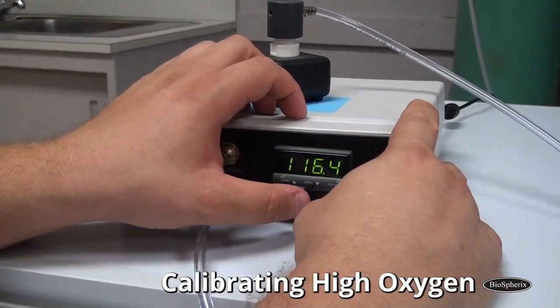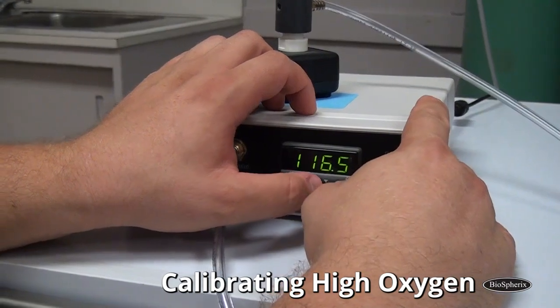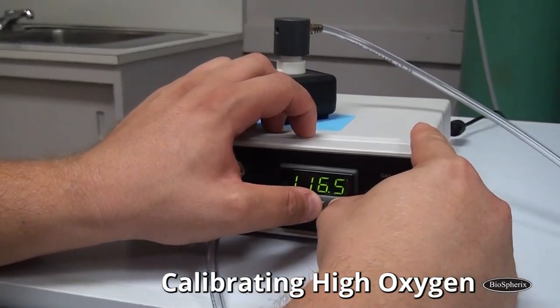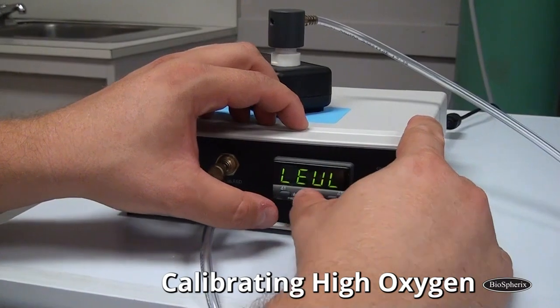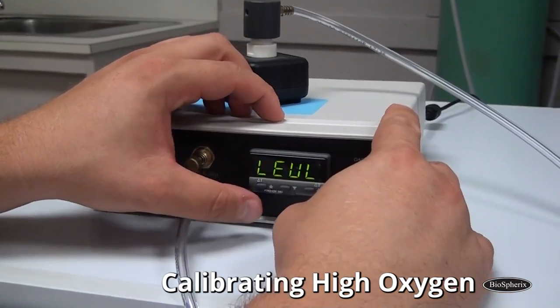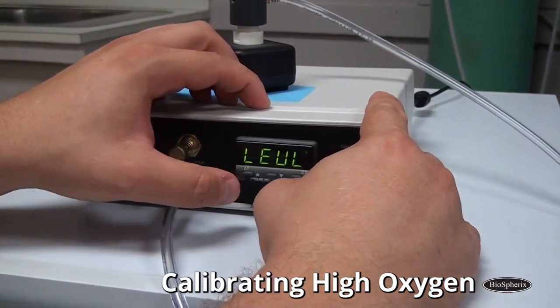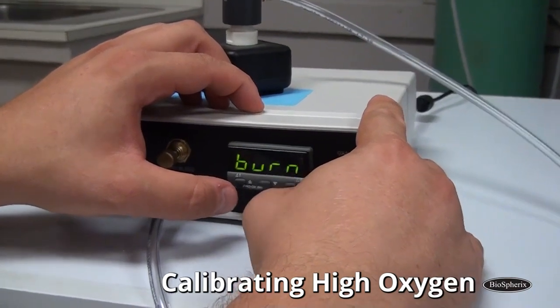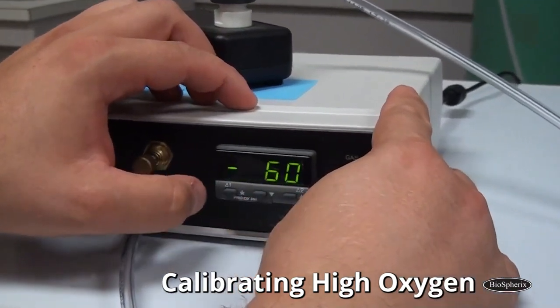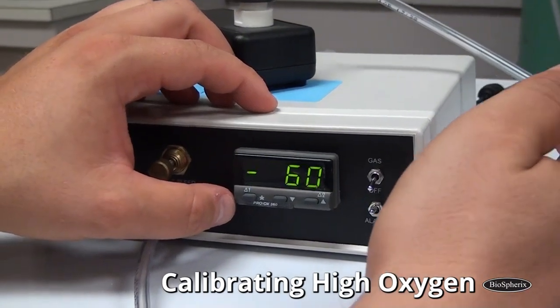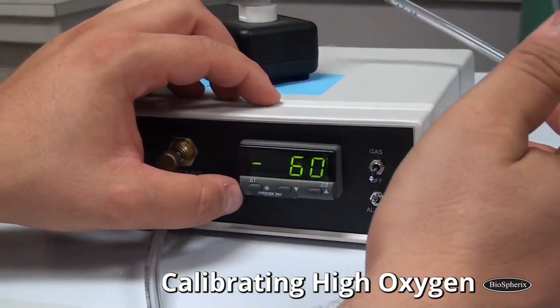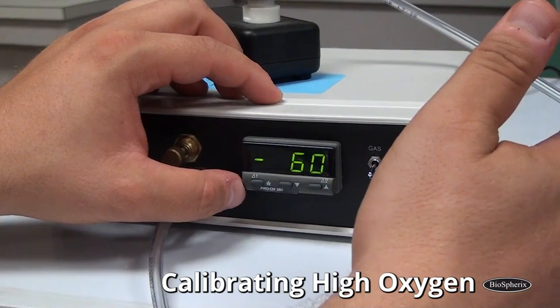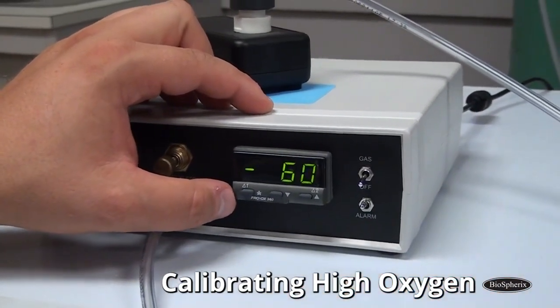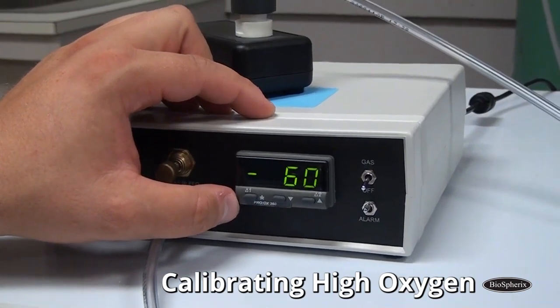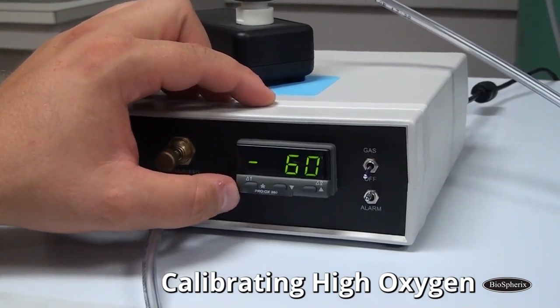It's a coarse adjustment. It's in the program mode, so we're going to hold up and down until we see tune. We need to go to the level function, so I hit down once, go up to level 3, and I just press up to go through the level until I see span. So I see minus 60 here. Again, it's a coarse adjustment. You might have to go back and forth a couple times. And when you're doing 100% oxygen, it's always going to have a little bit of inaccuracy. So you just get as close as you can.